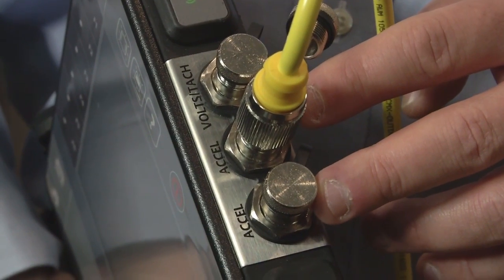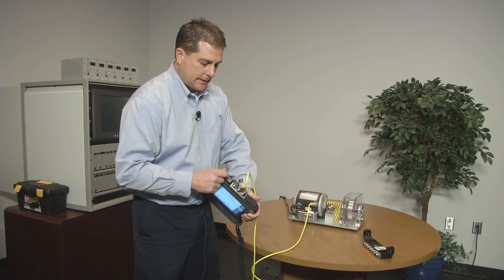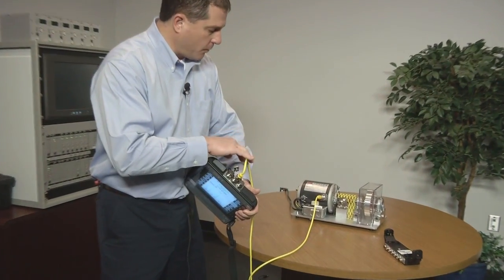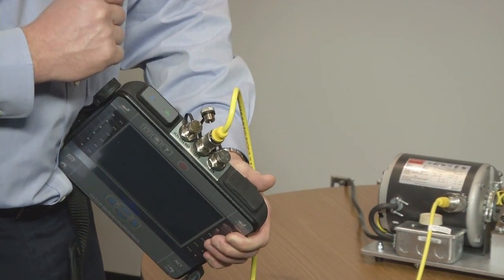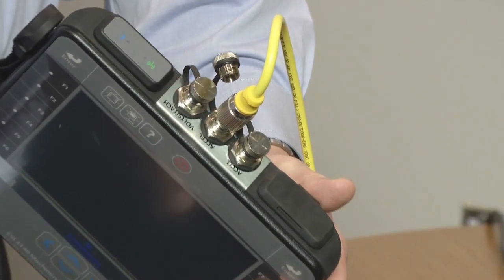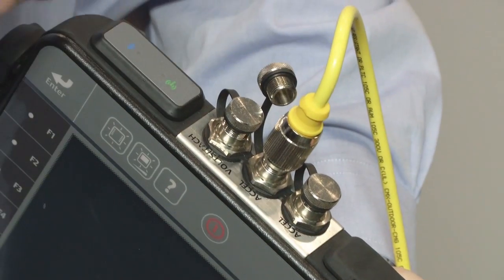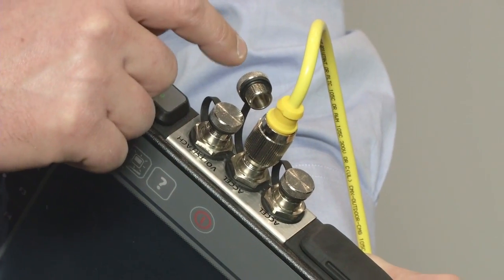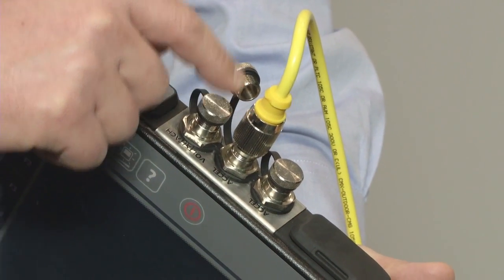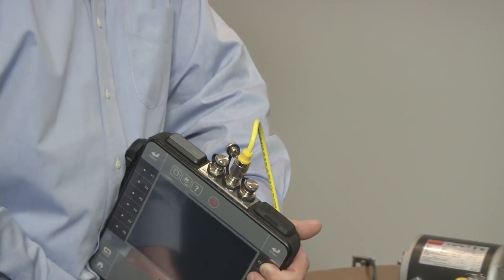The top of the unit has two connections for accelerometers. This is a four-channel instrument, so we can connect up to four sensors. I only have one tri-axial accelerometer connected currently, but we could connect up to four individual single-axis accelerometers. I also have the volts/tach connector, so not only can I have four simultaneous channels being recorded at the same time, but also a fifth input from the tach to get phase, which is very important for analysis techniques and various tests.